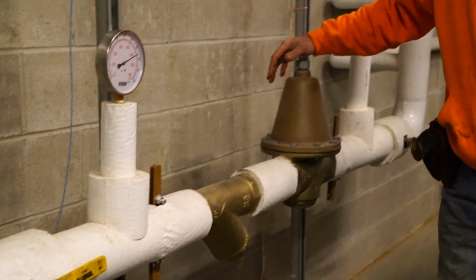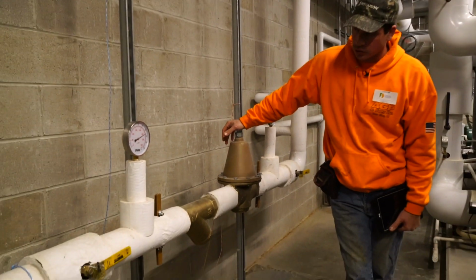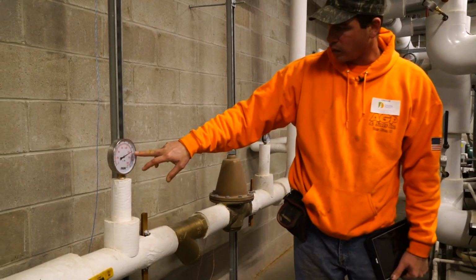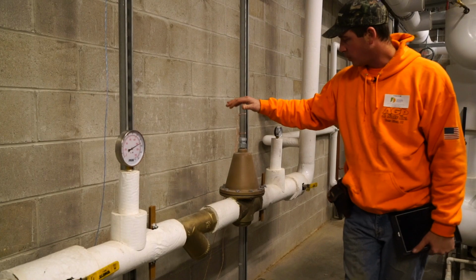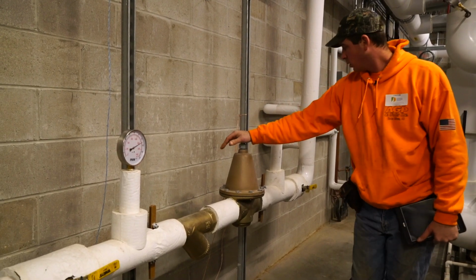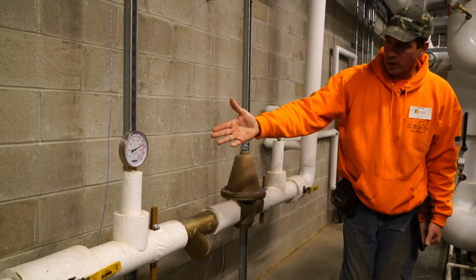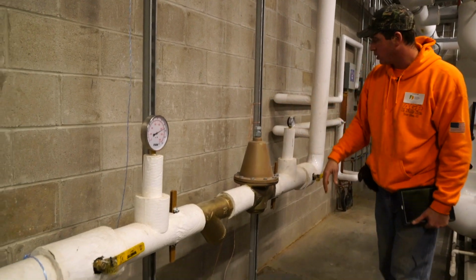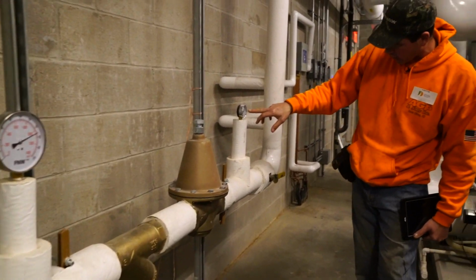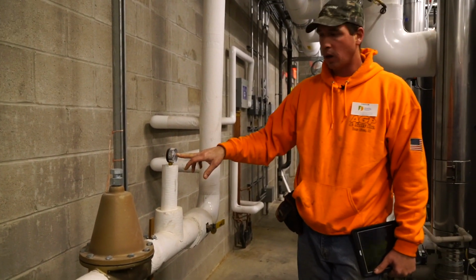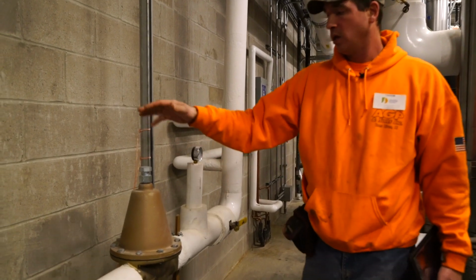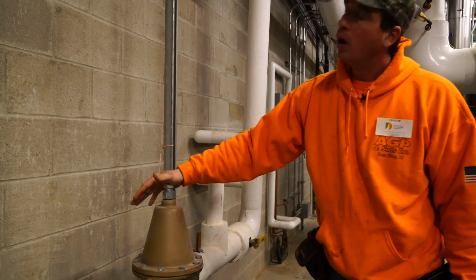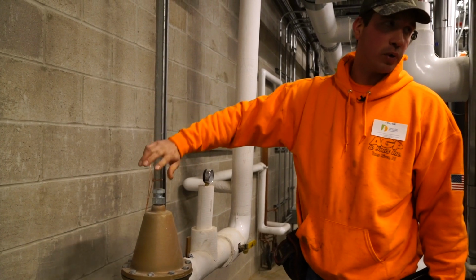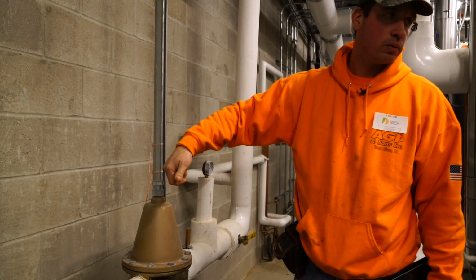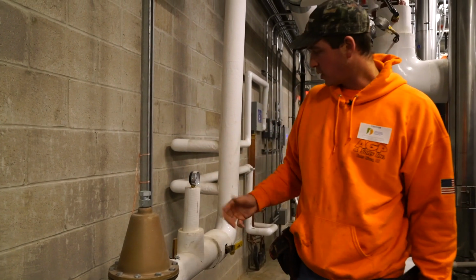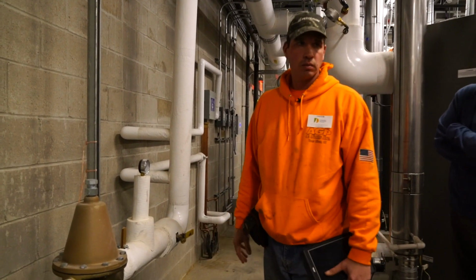The pressure for the water coming into the building was extremely high. You're at 150 pounds. So we have a pressure reducing valve. So before the valve, you got your incoming water pressure, 150. On your building side, you're at 70 pounds. If you ever want to adjust this, this is your set screw on top. Take it out, increases pressure, screw it down, decreases pressure. But you're at 70 right now. That's common? That's good.